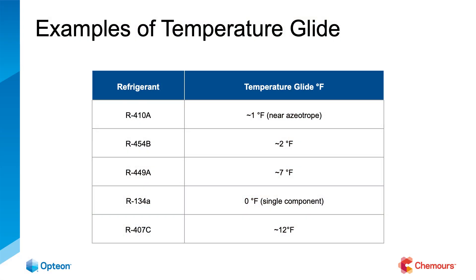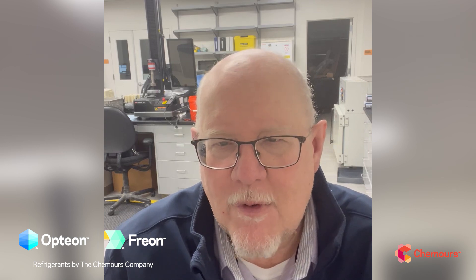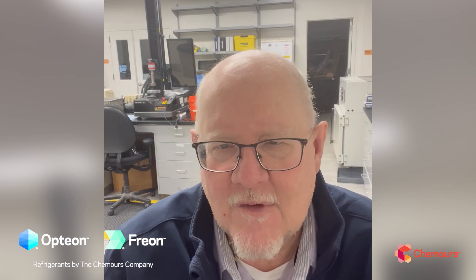Let me talk about temperature glide a little bit. Glide for 454B is about 2°F, where 410A was around 1°F or even a little less — very minimal, not something we have to be overly concerned with. If you look back at refrigerant history, we've been very successful with things like 407C, which has about a 12°F temperature glide. So all the good practices we use — take liquid out of the jug, use the dew point when calculating superheat, and top off refrigerants if they need more charge in the field — are certainly appropriate and acceptable and won't show any detrimental performance.